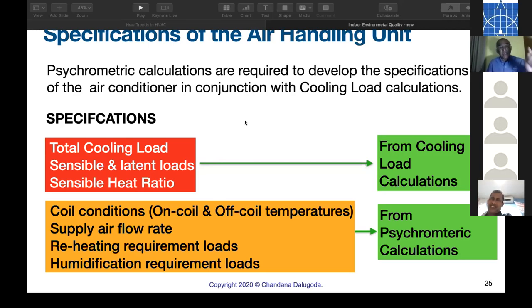Then you have another bit of specification left, that is coil conditions, on coil and off coil. How do you find this? The best way is psychrometric analysis. You can plot it and get it from the psychrometric chart. Of course, in the early days Carrier had mathematical calculations to find this, but psychrometric is the best way. Supply air flow rate, how do you calculate? You use Q equals m Cp delta T, but still you need psychrometrics to find this.